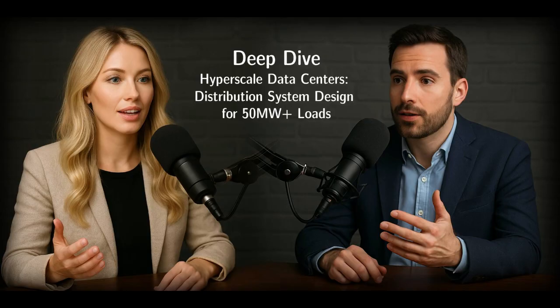For the bigger loads, where are the technical walls you hit? Oh, the walls are significant. Let's take that 75 megawatt example again. At 12.47 kilovolt, that's a current of 3,470 ampere per phase. Wow. That requires multiple really big conductors, minimum 750 kcmil, probably several circuits of it. Just managing the physical space for that is tough. And then voltage drop becomes a huge issue. You could easily see 3 to 5% drop at full load without spending a fortune on regulation equipment.